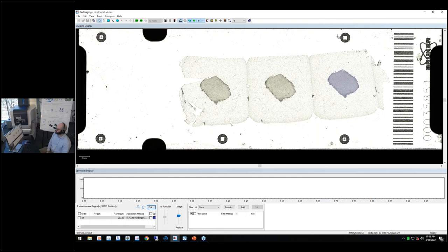And then the last question there was, can one perform multi-layer imaging if needed? Yes, you can. And this is another thing that when we go through training with new users, we educate how to go about doing this to build an effective analytical experiment that can go over the same piece of tissue up to 5 times. Typically, we recommend that you use a larger spatial resolution in an experiment like that in order to leave behind some tissue so that you're able to ablate more material within the pixel as you go through. So I hope that answered the question.